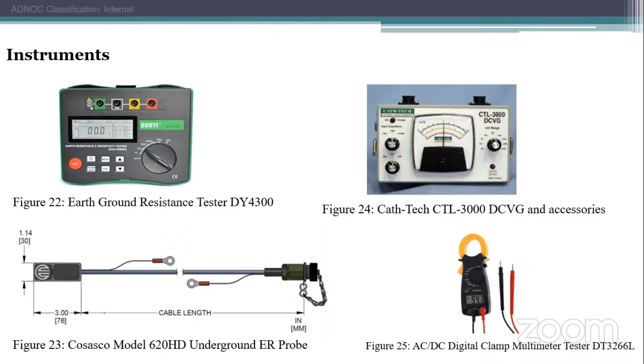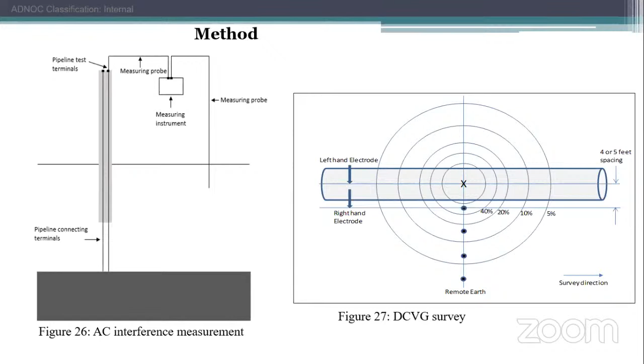This is a schematic. Figure 26 shows the pattern in which AC voltage was measured, showing how much AC voltage was introduced in these pipelines. The DCVG is used to check if the pipeline's coating would allow this corrosion to happen. This is me doing a soil resistivity test.